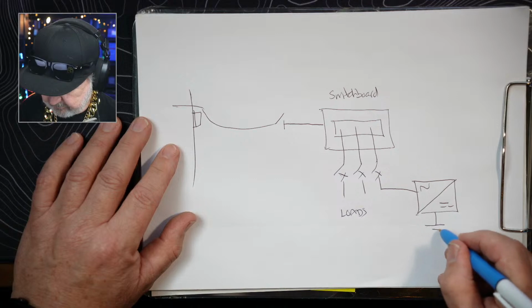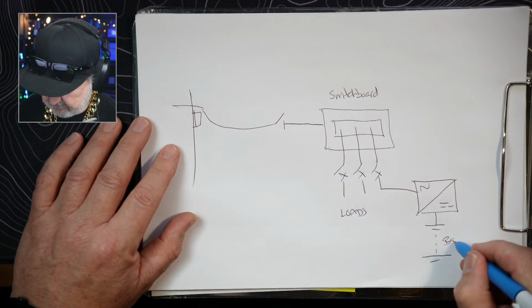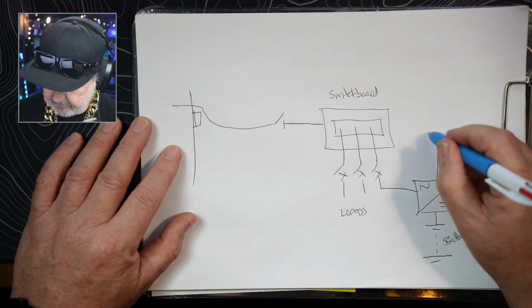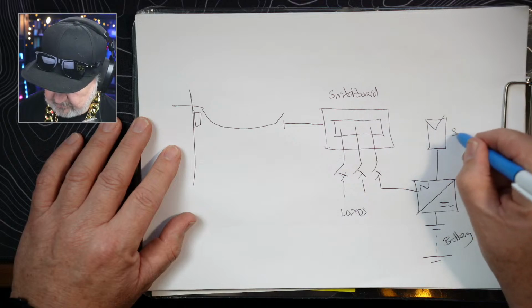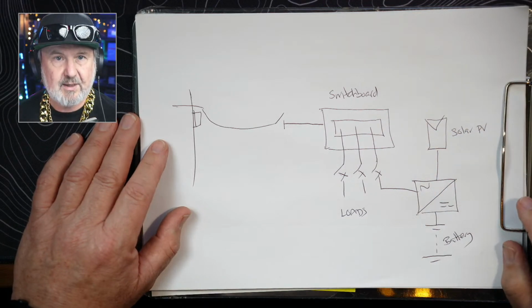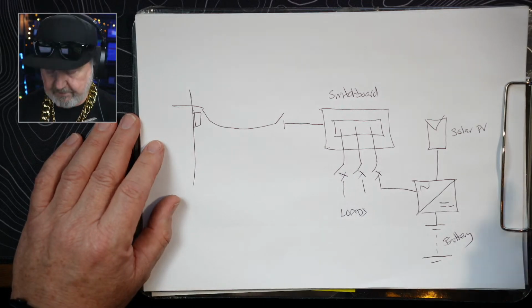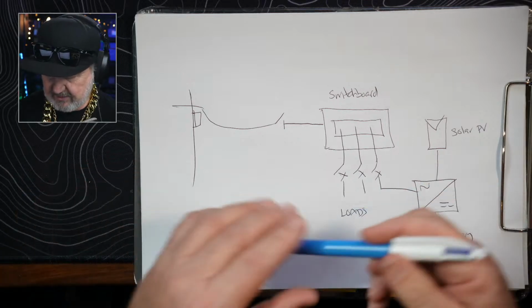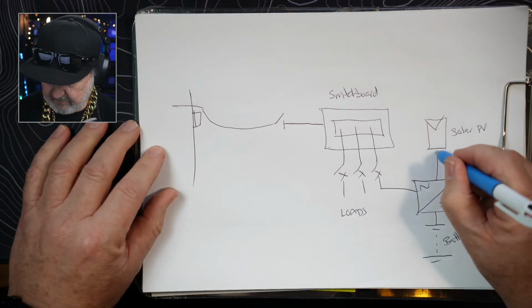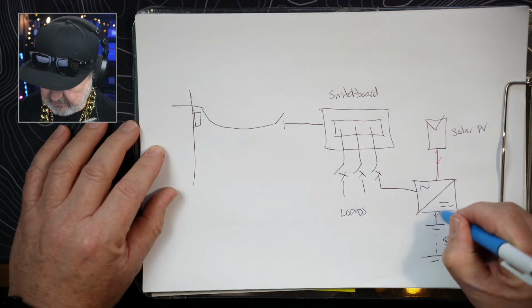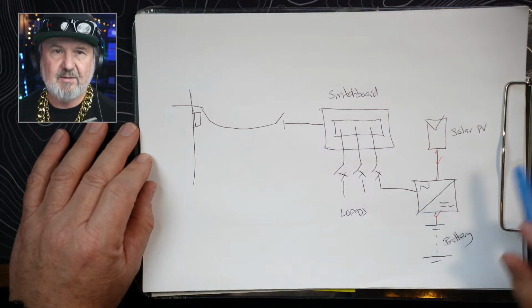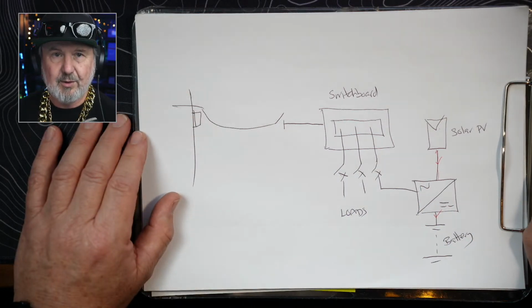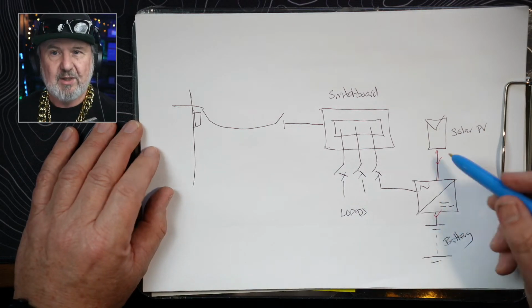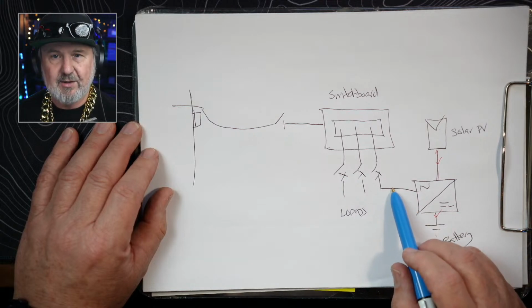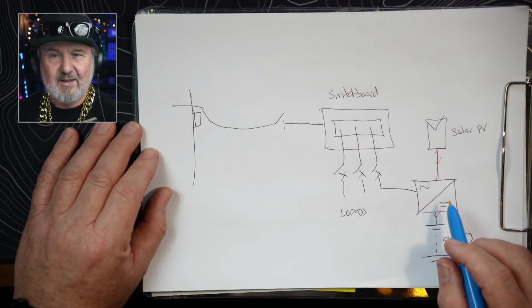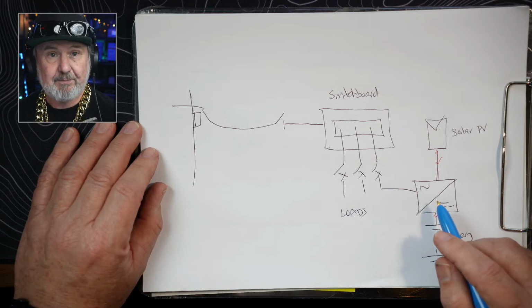It's got a battery, that's the battery there. It's also got solar - that's the symbol for a solar panel, a photovoltaic solar panel. What that means is this is DC coupled. The energy from the PV array can flow directly into the battery through the inverter's DC-DC conversions. It doesn't actually need the grid to work, so it can still charge the battery. But when it's charging the battery, it's not exporting power out to the grid, so it's not pushing up grid voltage - as far as the grid's concerned, it's not a generator, it's just charging a battery.